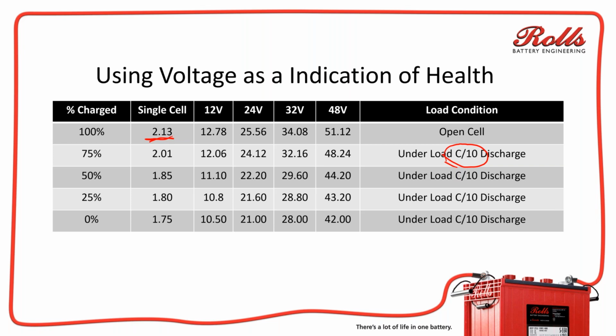You can't control current going into the battery in the absorption or the equalization stage. Ideally, you've done a full bulk absorption charge before you do an equalization, because you don't want a lot of extra current in equalization, because the batteries are already getting hot, or hotter than you really want.